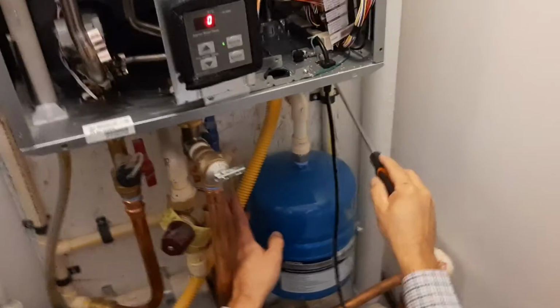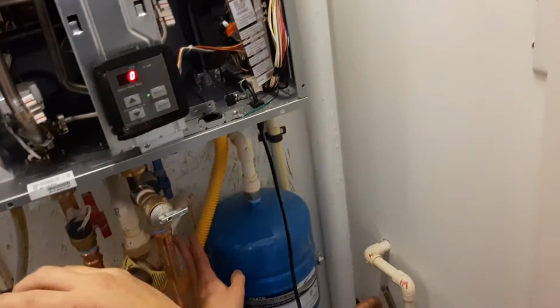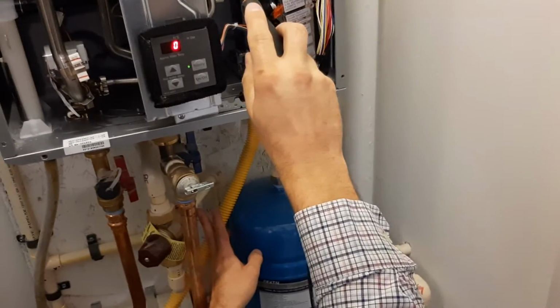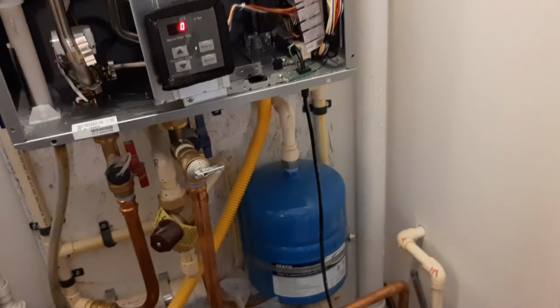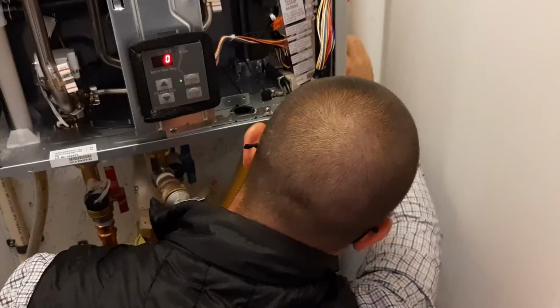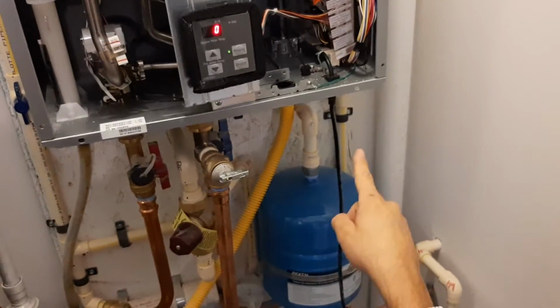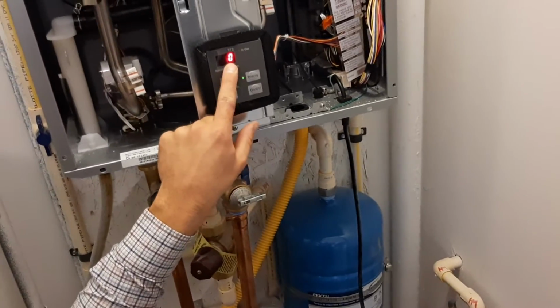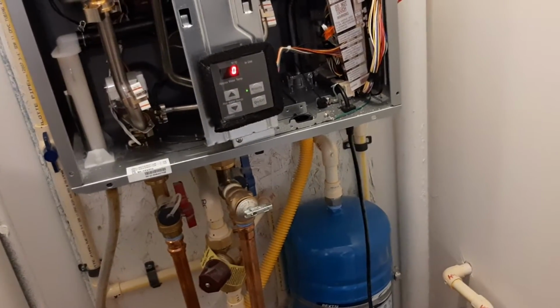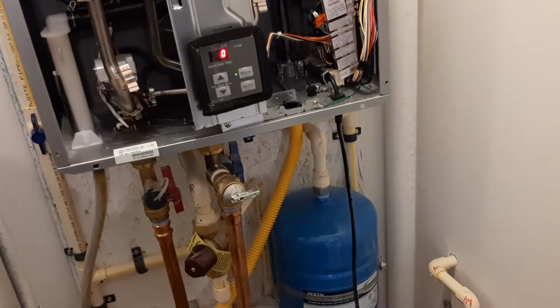And often what happens is it's easier to go up and through that coil than it is to go up and through this coil, because this coil is much smaller. So an easy way would be: don't allow it to go through that coil. If you do that and all of a sudden you register a flow rate, you know it's a leaking check valve. That's typically what we'll do to check it -- shut the coil off.